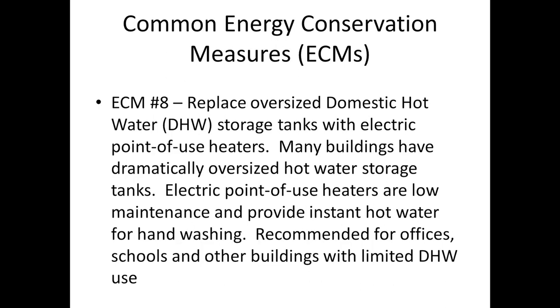In commercial buildings, this is actually becoming a really common recommendation for us, especially in schools that don't have showers and office spaces. A lot of times, just a big 200-gallon or 130-gallon hot water tank is installed. Most people wash their hands really quick, in under 5 seconds or under 30 seconds, and don't even give a chance for hot water to be used, but you're constantly heating 120 or 200 gallons of hot water. So we recommend in these cases where you're just using a sink to install an electric point of use instantaneous heater.